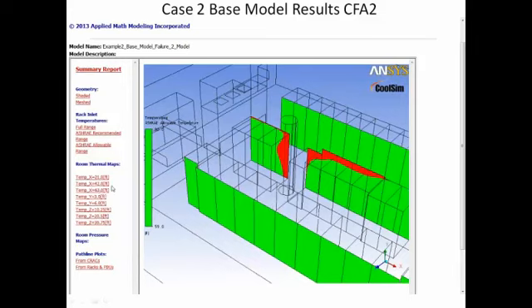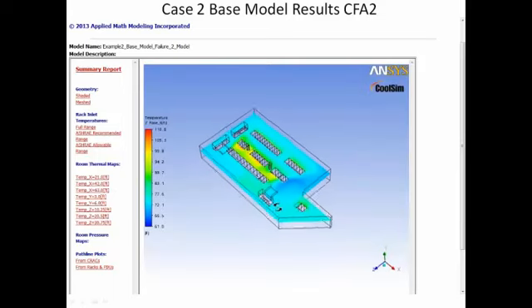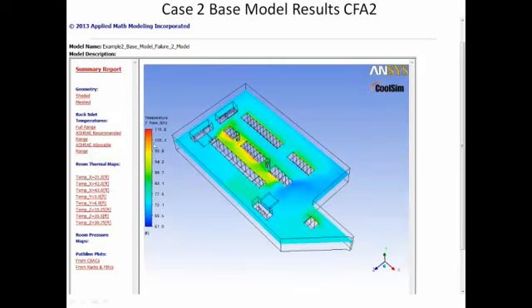And if we take a look at any of the cross sections here, let's say at 6 feet, we're going to find this data center is warm. I mean, it's showing it to be upwards of 110 degrees on the hot side. It's going to be in the 90s in this section of the room. That's going to cause failure mode conditions to exist.